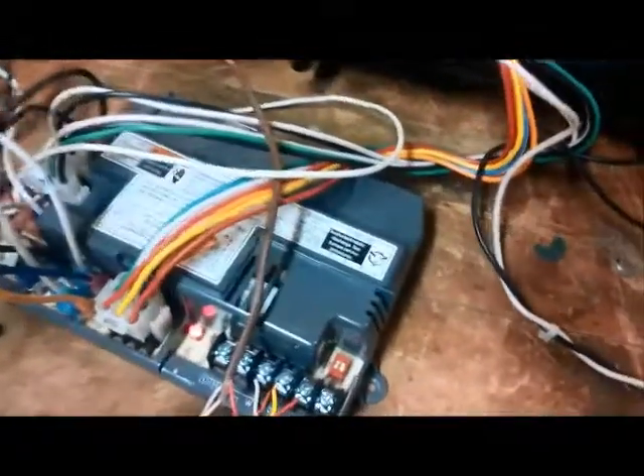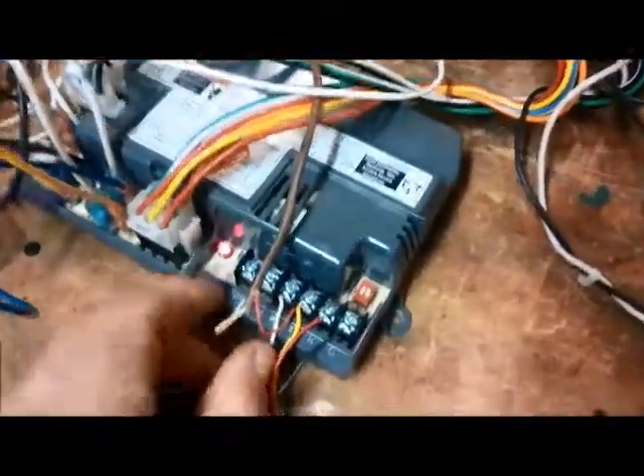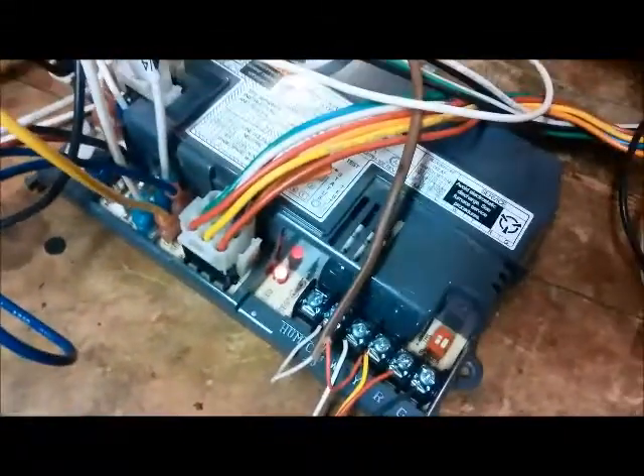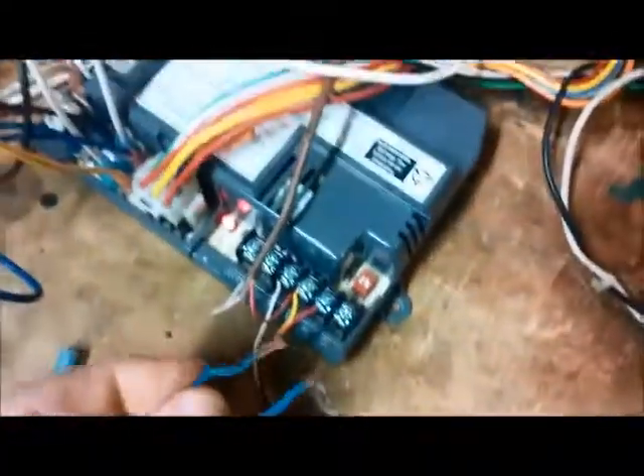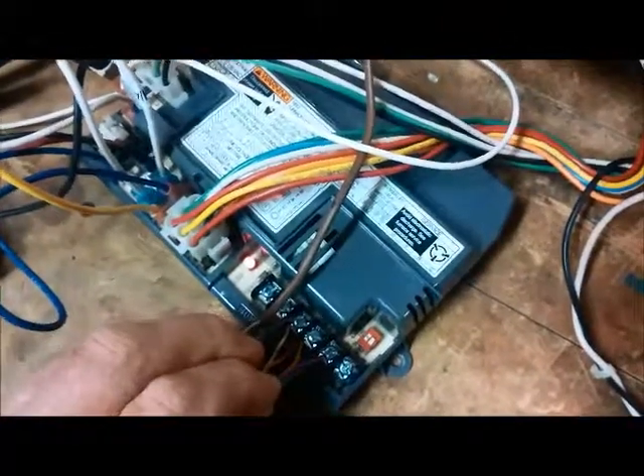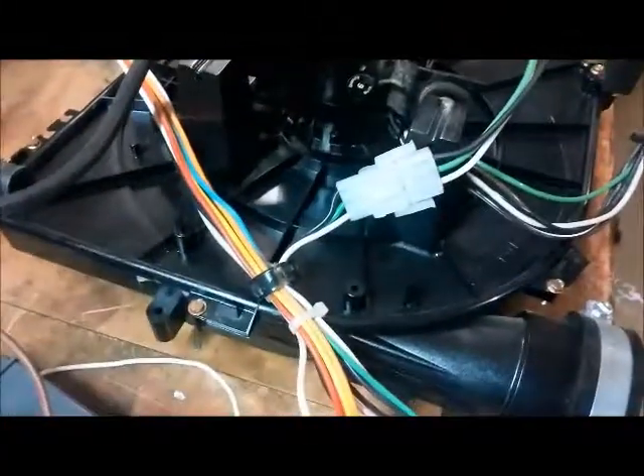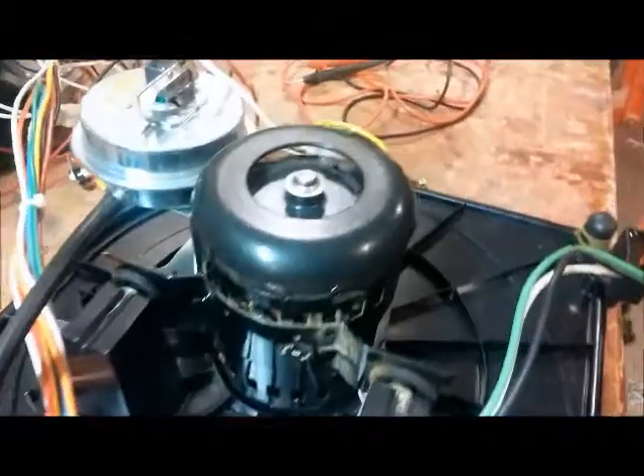What else? You could check to see if your thermostat's working by jumping the R to the W and see if your heat comes on. A lot of calls are, I don't think my thermostat's working right. Well, you can either jump W to R right at the thermostat, or you could do it at the board right here. And then your inducer motor should run. First thing that happens on a call for heat.